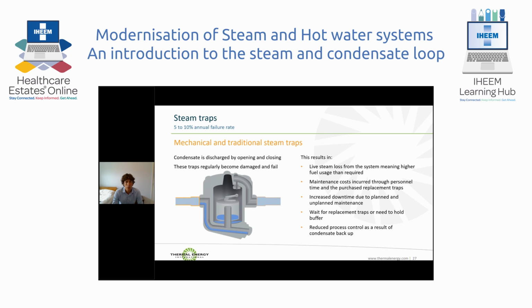As I mentioned earlier, when we're using steam, we are taking the energy from the phase change of steam to condensate. That means that once the energy has been given up, the steam turns into water and we need to discharge it. In fact, in most other languages, the steam trap is more correctly called a condensate drain. These steam traps are traditionally mechanical devices operating on a variety of different principles.